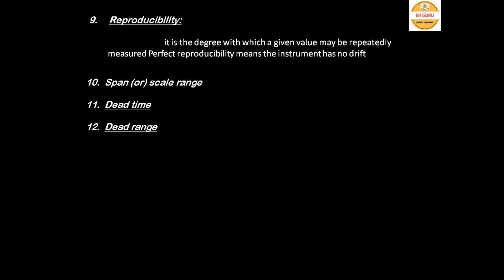Dead time is the minimum amount of time taken by the instrument to respond to a change in input — it may include the time taken to overcome the inertia of the instrument. Dead zone (dead range) is the range up to which the instrument will not respond at all. These conclude the static characteristics of an instrument. Dynamic characteristics will be covered in the upcoming videos.